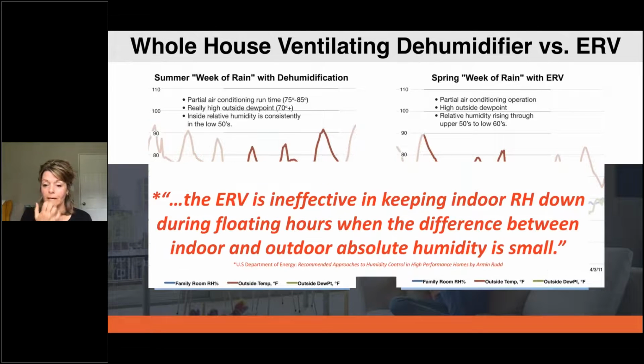Armin Rudd did a study with the DOE, and basically what he said is the ERV is ineffective in keeping indoor RH down during the floating hours, which a lot of times is our overnight, mornings, shoulder seasons, when the difference between the indoor and outdoor absolute humidity is small. So it's humid inside, we're not running a lot of air conditioning to dry that air, and it's humid outside.